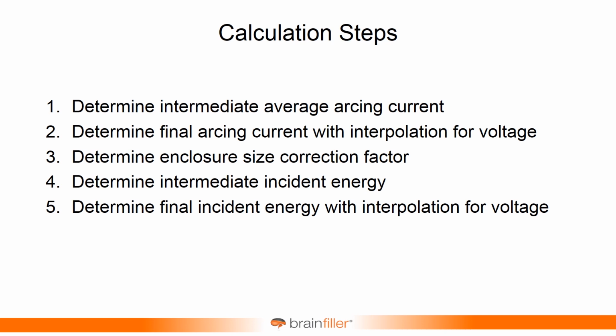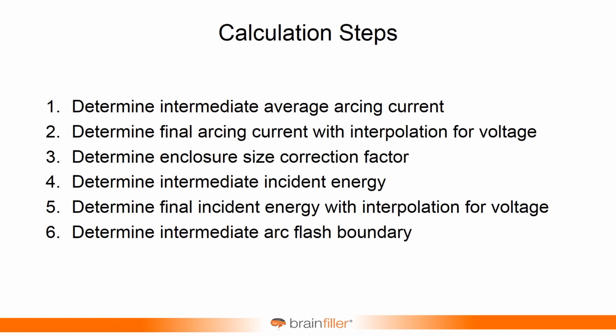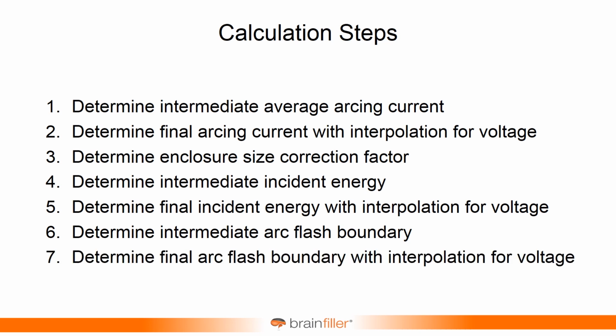And then you calculate the intermediate arc flash boundary. Again, it's basically just saying the 600, 2700, or 14.3 kV version of the arc flash boundary. And of course, then you go back and you interpolate for the actual voltage. So it's much more precise to be able to handle it this way.